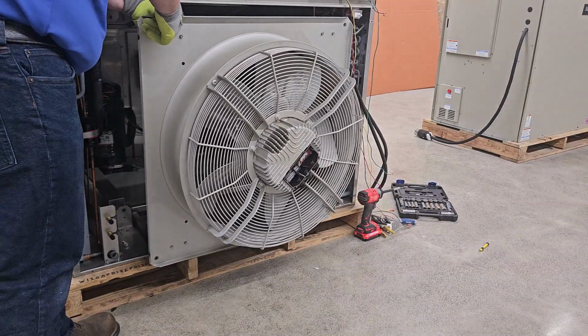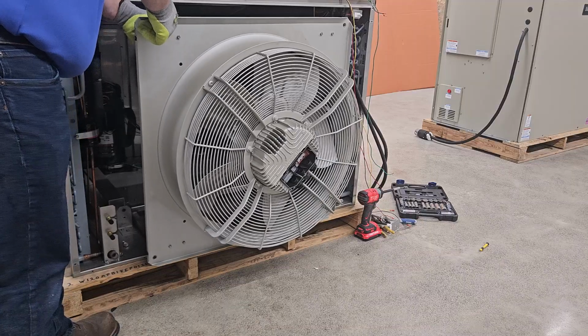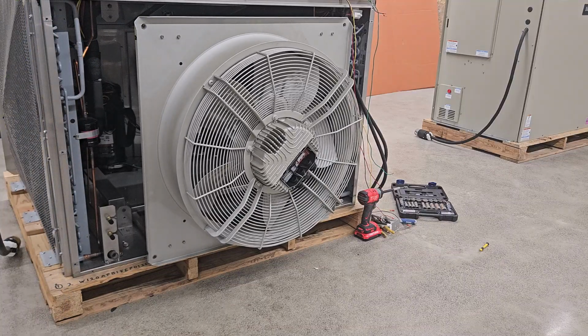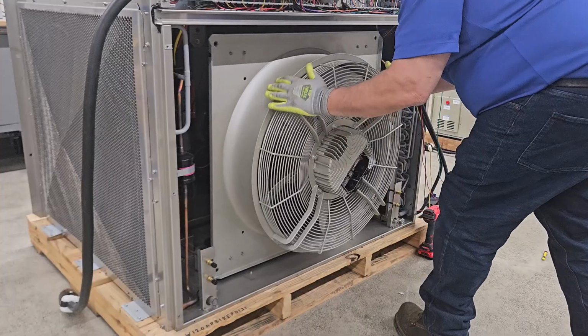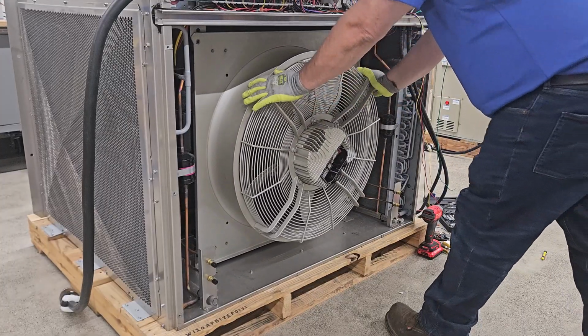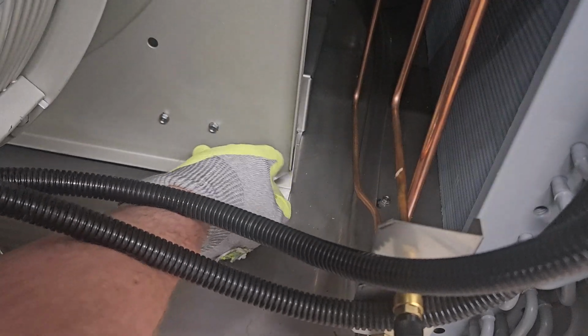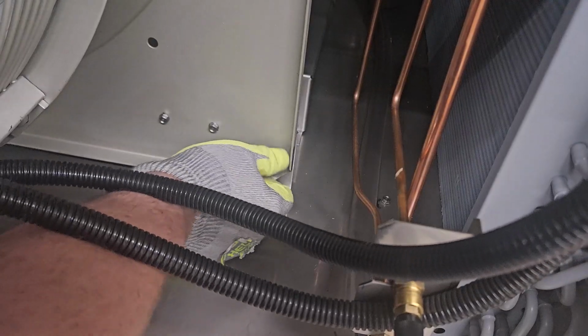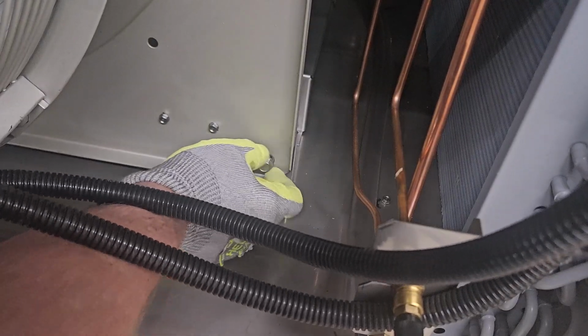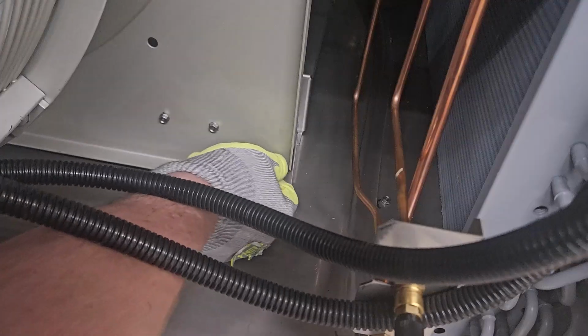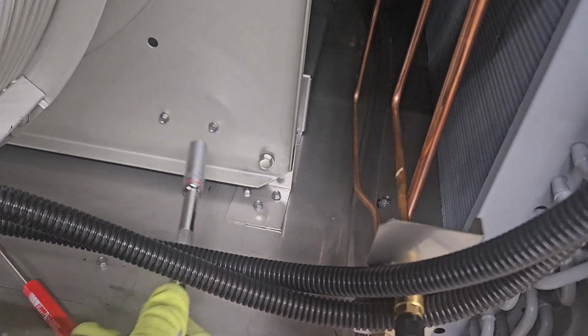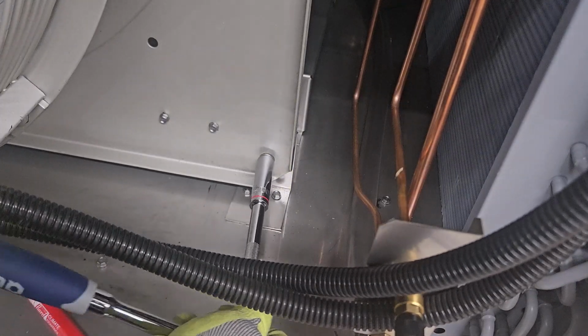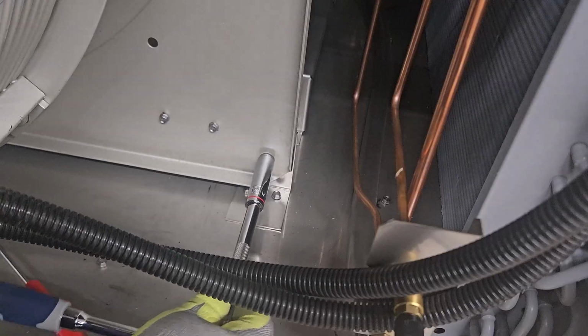Pivot the assembly back into the locking position on the roller bar and push the assembly back into the MEGA-TEC condensing section of the unit. Reinstall the 4 mounting bolts into the assembly. At this point, you may want a breaker bar or something to give you leverage to move the assembly into position so the bolts can be installed without cross-threading them.